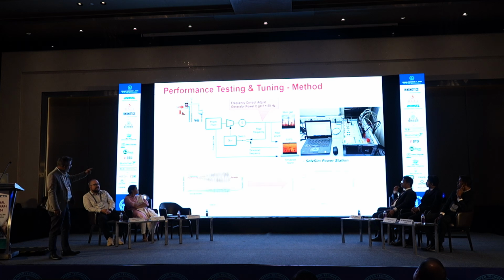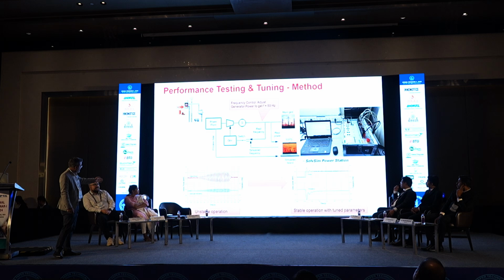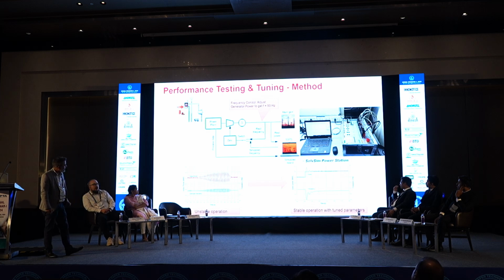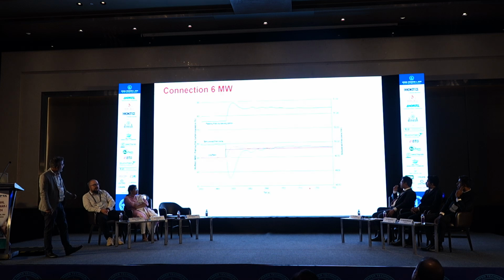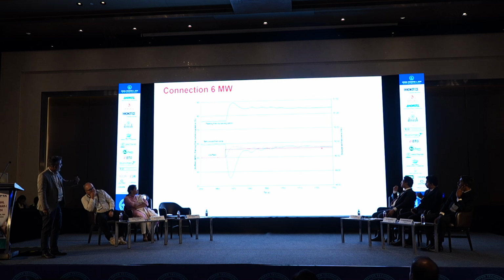So here in this particular case, when we started the test, there were a lot of oscillations in the output power and grid frequency. Then we tuned the governor PID parameters using the Ziegler-Nichols method, and we achieved stable operation with tuned parameters. Let's see one of the graphs of the test that we carried out there. The green trend which you see here is the simulated frequency. Initially the turbine was running at 50 megawatt. We gave a load step of 6 megawatt with a connection of 6 megawatt.